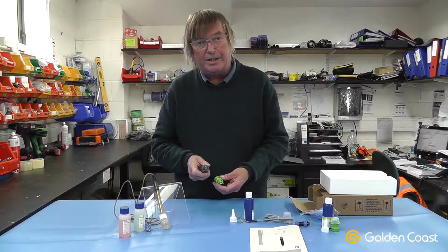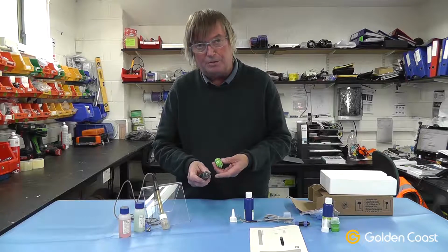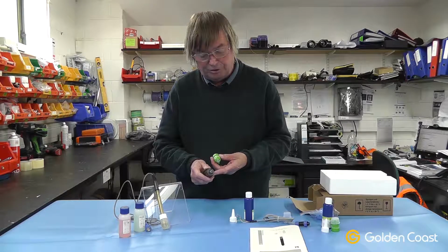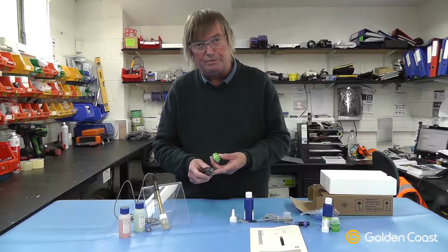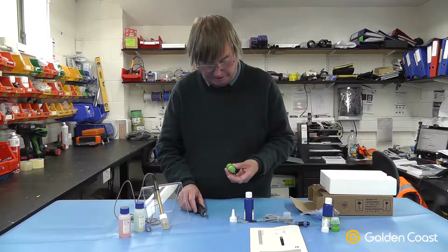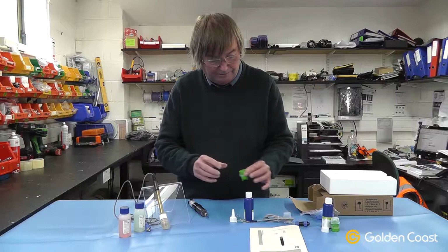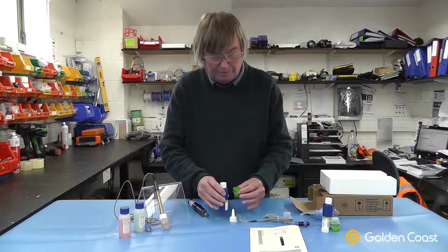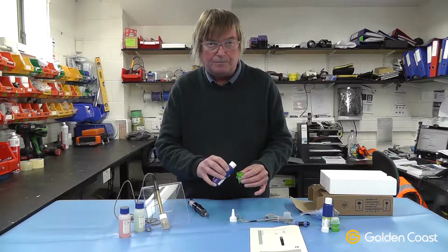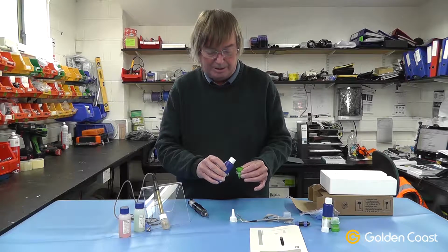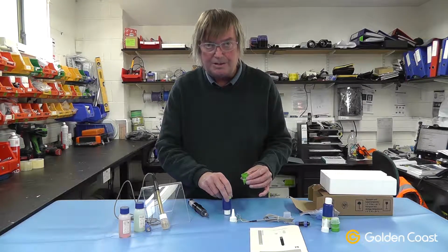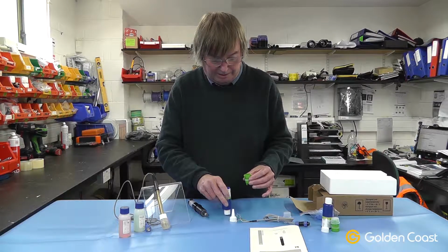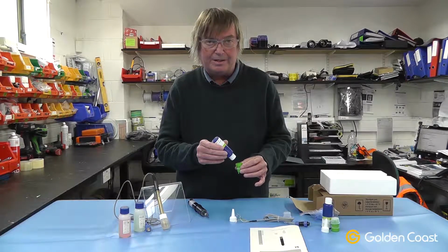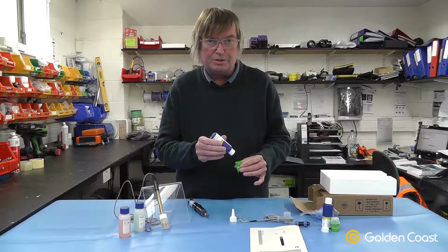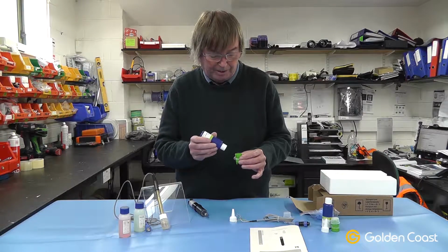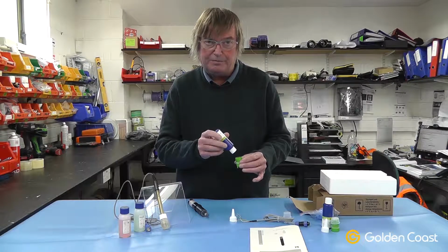and if you're just checking it for calibration or anything, make sure the probe is nice and clean and tidy, and has no corrosion. If it's marked or corroded in any way, it should be returned to be refurbished. You then, with the cap in your hand and your gloves on, use the electrolyte gel with the filler cap to fill the cap up, and there must be no air bubbles in this, so it's good practice to store this gel upside down because it is quite thick. You then squeeze it into the cap very, very gently, very slowly, making sure there is no trapped air inside the cap. When you get to the bottom of the threads, that should be enough gel in there now.